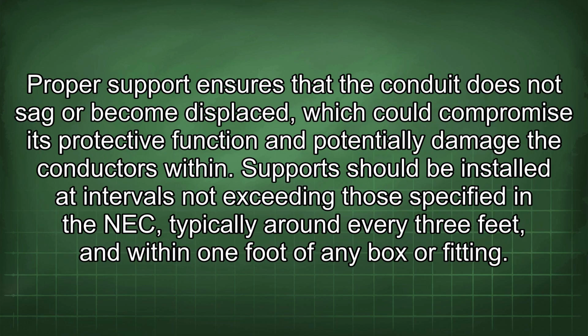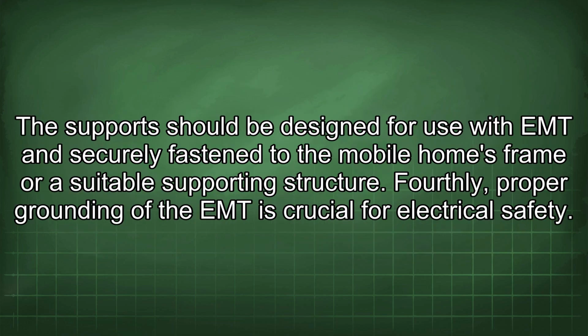Proper support ensures that the conduit does not sag or become displaced, which could compromise its protective function and potentially damage the conductors within. Support should be installed at intervals not exceeding those specified in the NEC, typically around every 3 feet and within 1 foot of any box or fitting. The support should be designed for use with the EMT and securely fastened to the mobile home's frame or a suitable supporting structure. Fourthly, proper grounding of the EMT is crucial for electrical safety.